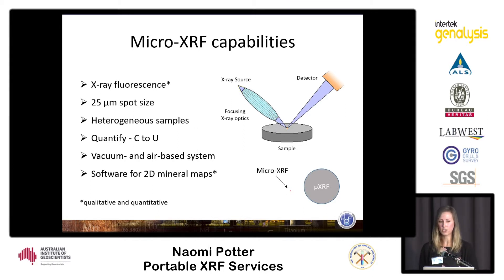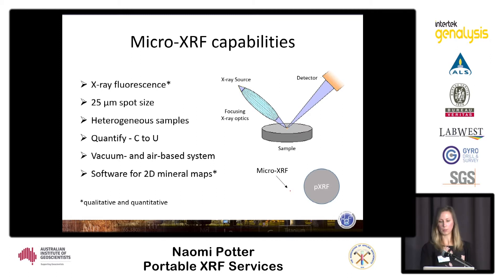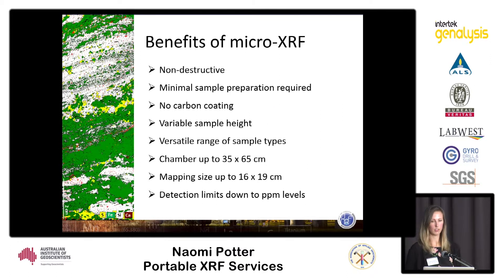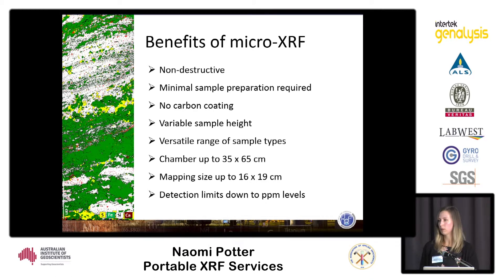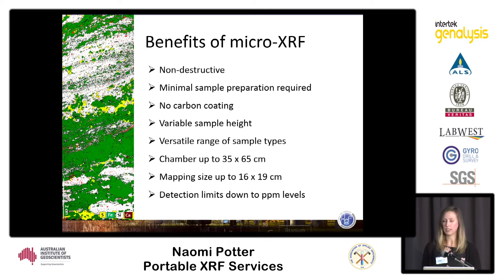The addition of mineral identification software enables you to turn this element information into mineral maps, which can be both qualitative and quantitative. The benefits of micro XRF include that it's non-destructive, it requires minimal sample preparation, and in some cases no sample preparation at all. It doesn't need to be carbon coated in the same way that an SEM sample does.